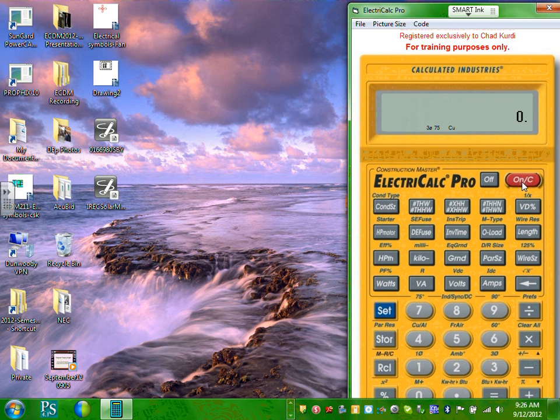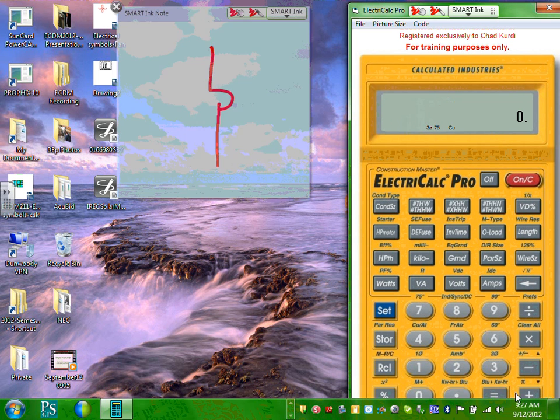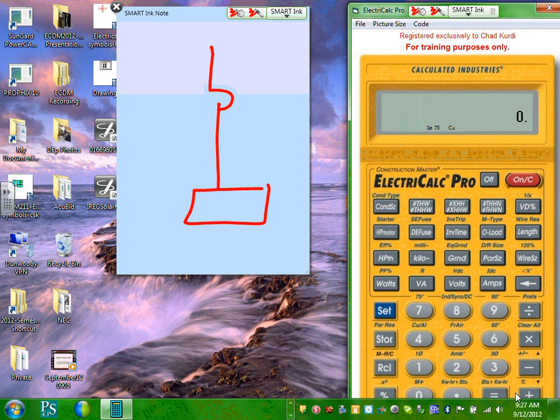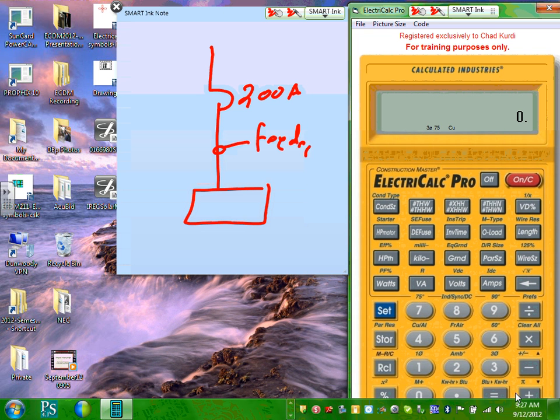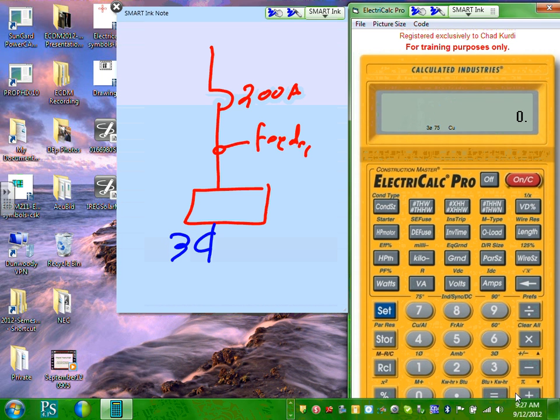Every time you finish an operation, hit C twice. Always. It deletes the memory. See what's on here? Hit it twice. Okay, let's go work on this one. So suppose I have this scenario. I have a panel, and here's my load. Suppose I have a 200 amp panel, and I need to size the feeder. 200 amp, we're going to size the feeder for a 200 amp panel. It's 3-phase, and it's CU, always copper. We're going to size the feeder to feed this panel, 200 amp. Cool? Everybody's okay with this?